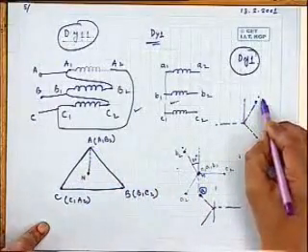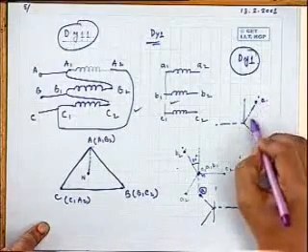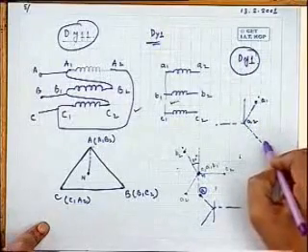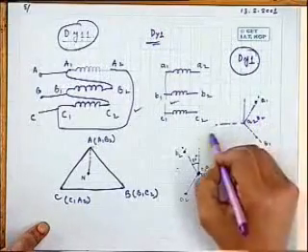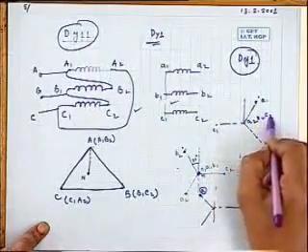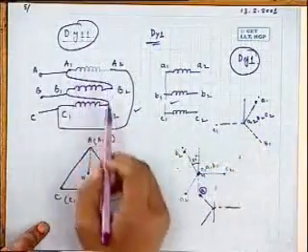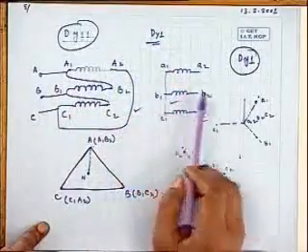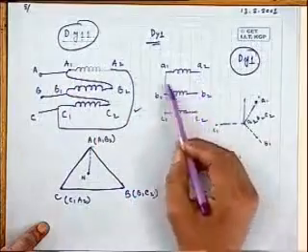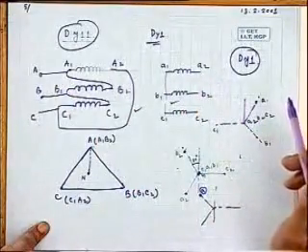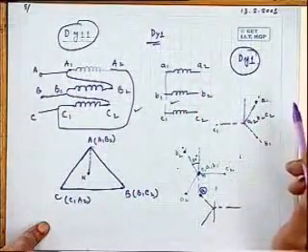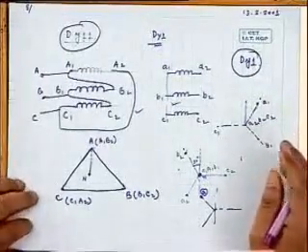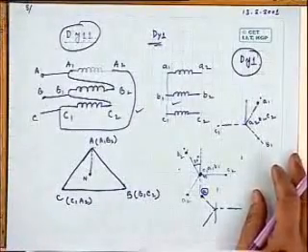Yes, it is available. A1, A2. Not only available, but with A marking. So this is A1, A2. This is also available, B1, B2. And this is C1, C2. That is, with this delta connection, you can realize Dy1. And in that case, you have to short A2, B2, C2 and take output from A1, B1, C1. I think you have got this.